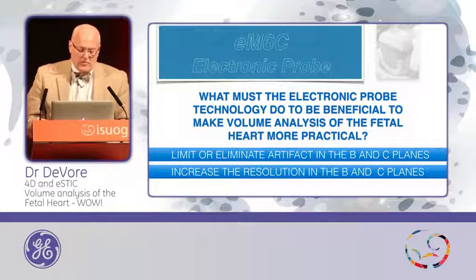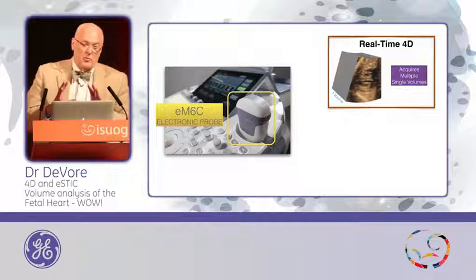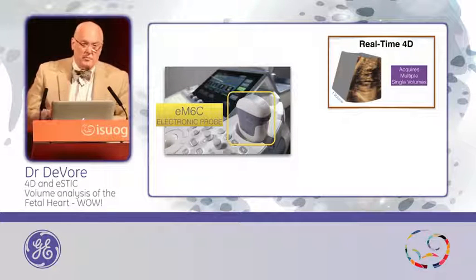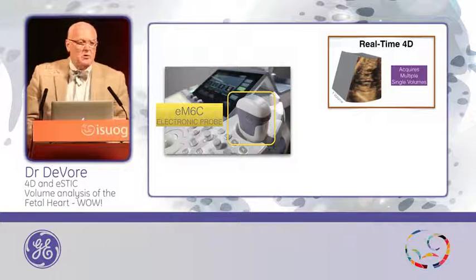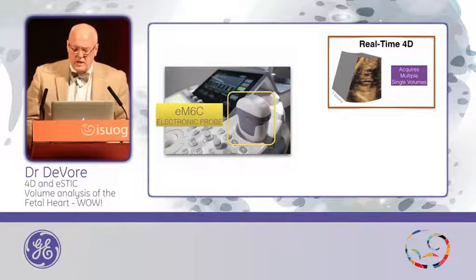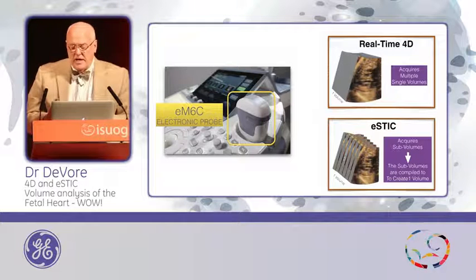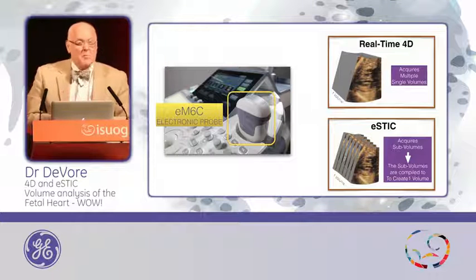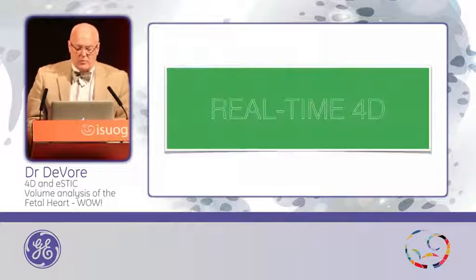Let's look at the two options this new probe offers. One is real-time 4D. In the past with the previous mechanical probe, the real-time 4D was there, but the frame rate was so low that it was really not very useful. Secondly, it offers E-STIC — E meaning electronic. With E-STIC, we have a chance to acquire, over a shorter period of time, higher resolution images by accumulating what are called sub-volumes to create the volume that we're going to analyze.